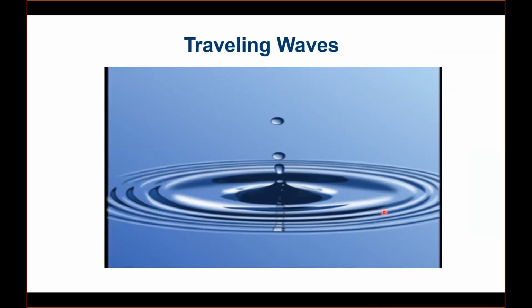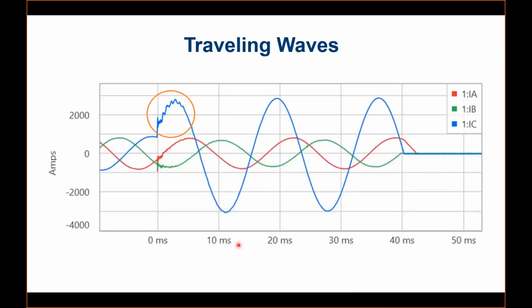The most important takeaway from this example is that the traveling waves will be much stronger at the point of disturbance where you drop the stone. And once they travel towards the edges, in all 360 degrees, their amplitude will decrease. We correlate this concept with electrical systems: whenever you have a disturbance, you have very minute transitions, or high frequency components, happening at the point of fault.